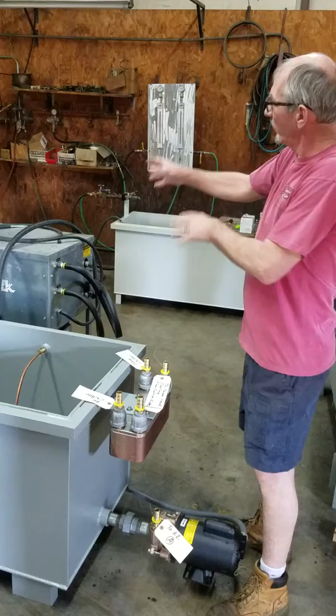Then we'll want a hose coming from the pump up to the heat exchanger, and then from the heat exchanger we'll want to go to the inside, which is the side that has the flow switch on it, of the water going to the cooling of the heads. And then from the cooling of the heads we'll want to dump in here to go back into the tank.